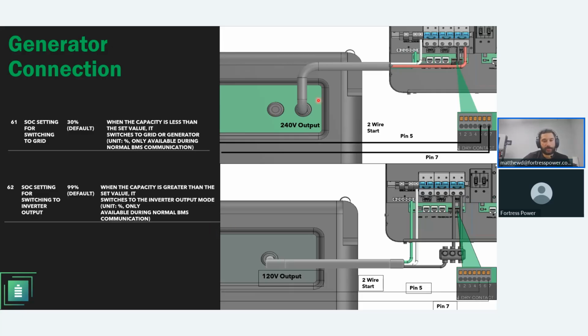For your generator connection, we do recommend the generator be an automatic, push button generator, because then you can tap in there to run the dry contacts from the inverter, from pin 5 to 7, to that 2-wire starter, or tap into the push button of those generators. Typical generators now are inverter generators that have a push button, and you can put that button in series so that when this closes, it engages the generator.